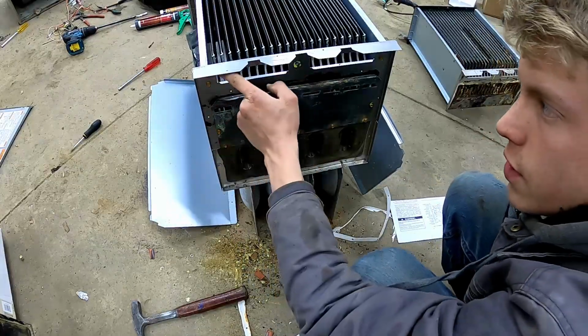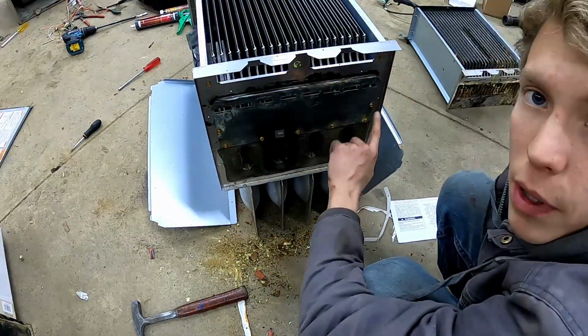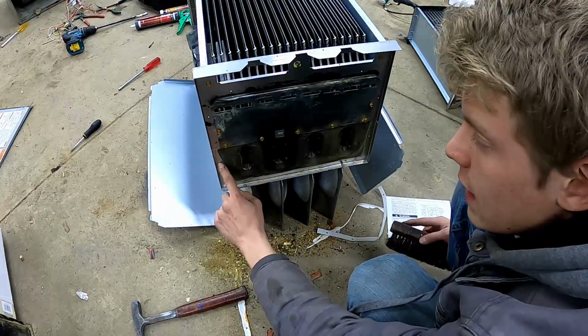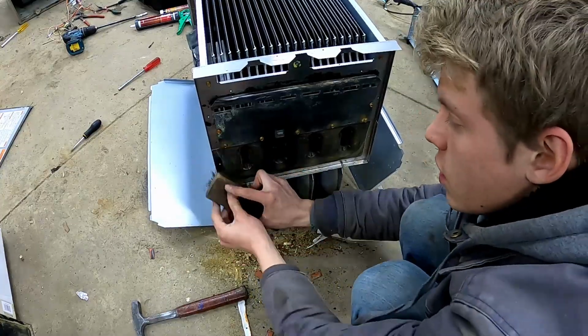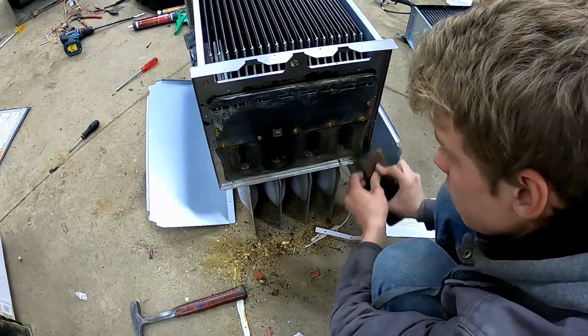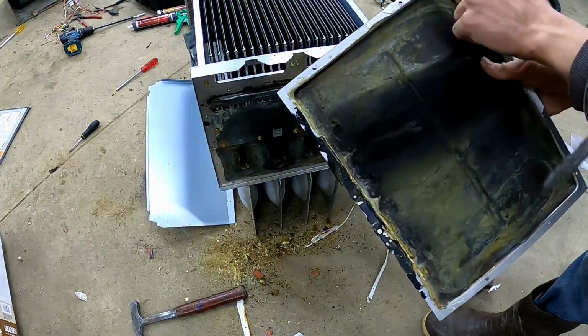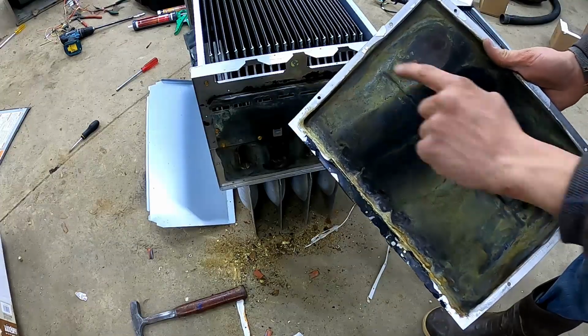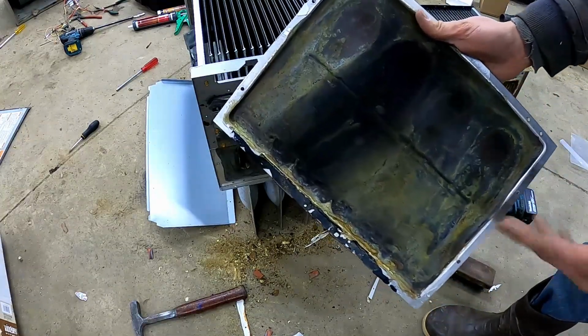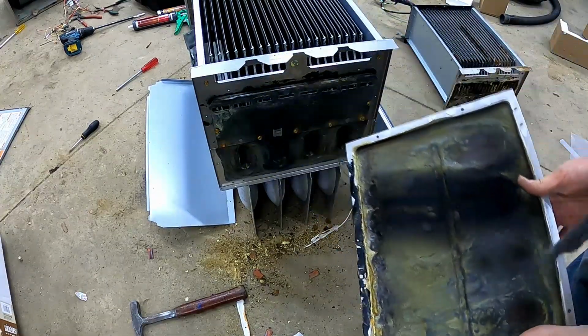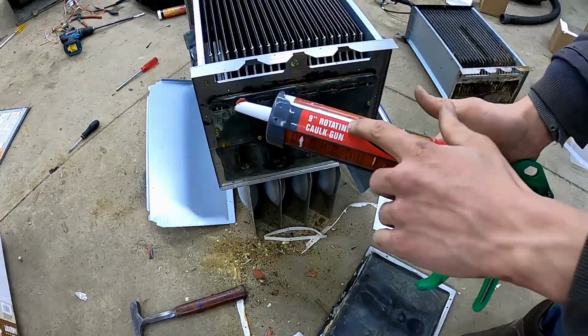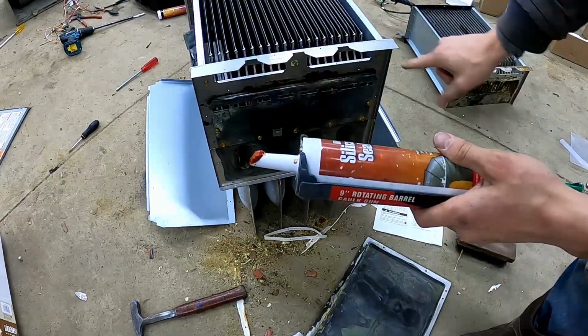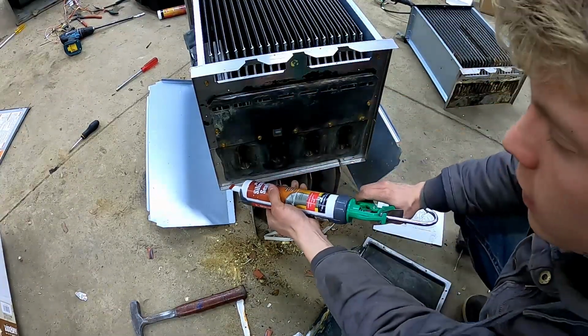Now this sealing surface is new, but you'll want to confirm that it's clean, and then you'll also want to clean this old sealing surface, which is not new. Also clean this sealing surface if you are reusing this plate, and clean the inside. If you're putting on a new one, then it should be already ready to go. You'll then take some high temp silicone and put it around the sealing perimeter.